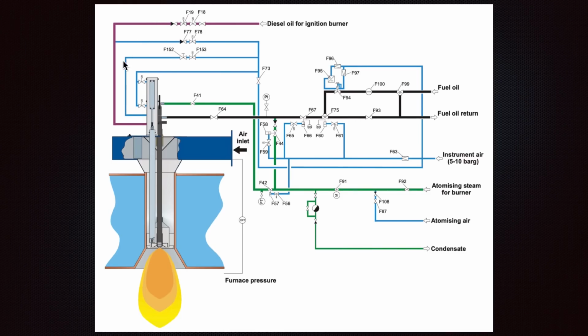After you verify all that and closely monitor each day whether something has changed, you can identify if there is any problem. These valves can also get stuck during the switchover between fuels, so you can check how they operate and see the symbols to know if the switch is okay.